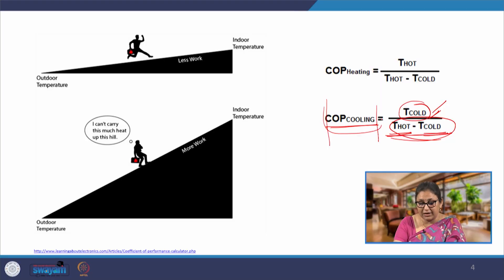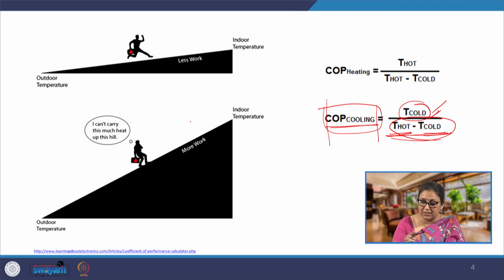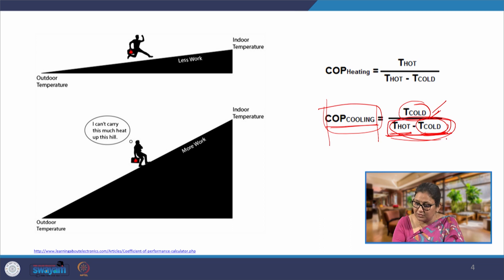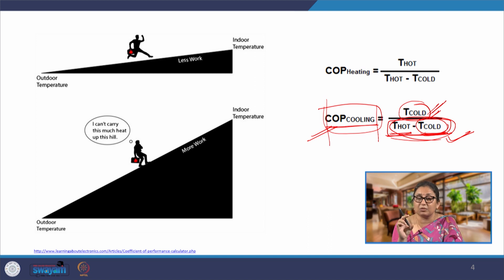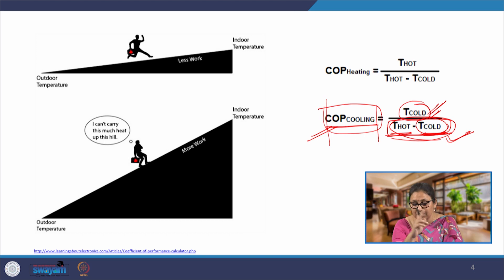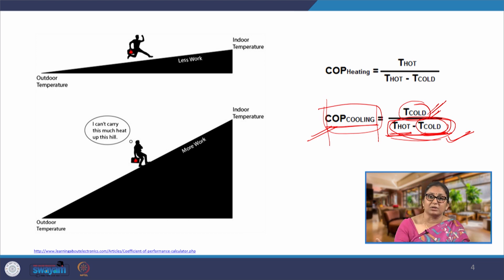When we are asked to check the effect of set point temperatures: we cannot change the cooling or heating degree days — they remain fixed by climate — we can only change the set point of the system. Depending on the set point, using the COP formula we can arrive at the adjusted COP and then calculate the energy savings. Reducing the set point temperature lowers T_cold, which raises the delta T and reduces COP; setting a higher set point for cooling (or lower for heating) reduces energy consumption, and we can directly calculate the resulting carbon emissions.